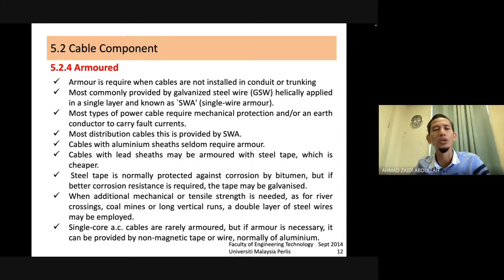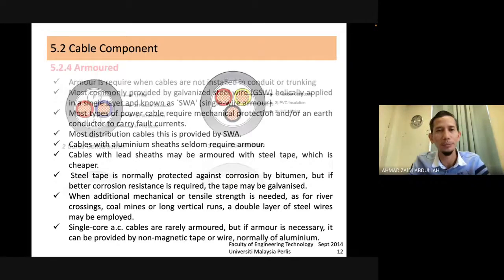So you can use a normal cable, but maybe after this you are working as a consultant or engineer, and you need to design some project related to this issue. So you need to remember that you must provide a double layer of steel wire. And then single core AC cables are rarely armored, but if armor is necessary, it can be provided by non-magnetic tape or wire, normally aluminium. Single core we rarely encounter.